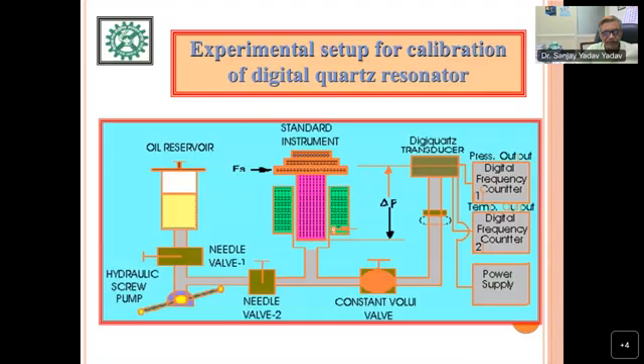This is a pump design. And now the next setup is for when you are calibrating a pressure transducer against a dead weight tester. You have to apply this experimental setup. Here a constant volume valve is not required. A constant volume valve is normally required in dead weight tester to dead weight tester calibration. For calibrating the transducer, depending on its output, in terms of frequency, in terms of voltage, or any other such as capacitance type, you need to have a power supply.